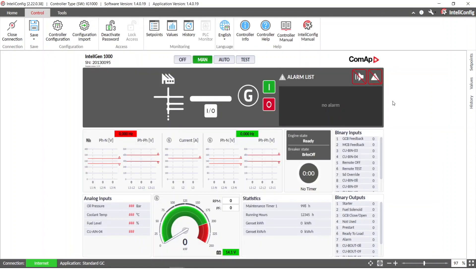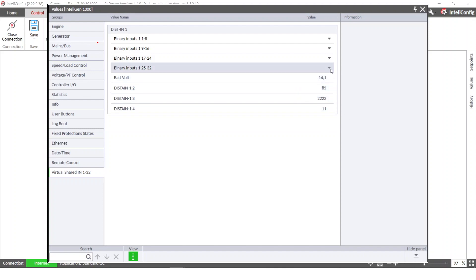CAN2 redundancy works for instances where there is a problem on the CAN2a line. If I unplug the CAN2a connector, communication will switch to CAN2b and the warning 'Redundant CAN Inconsistency' will show up. But as you can see, all the values are still visible and available for the second controller.